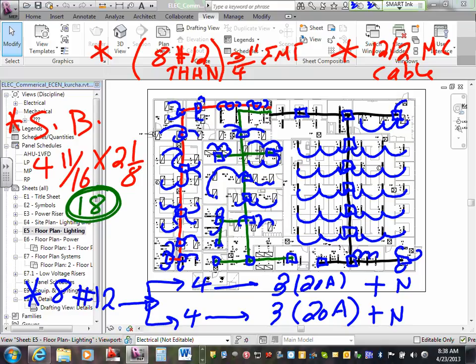Now you can argue I could have gotten away with fewer boxes here, but I usually do every 6 fixtures, throw a box in between them. Every 6 fixtures, throw a box. Okay, you might not use all of them, guys. The openings that you have in this box, you have 3 on every side, right? So you have 4 sides, 12 openings. You always want to leave 2 for the conduits. These 2 are going to be for the conduits, going in and out. The rest will be places where you can tie your MC cable. There's one little problem. This box cannot handle more than 18 conductors. So don't bring a lot.